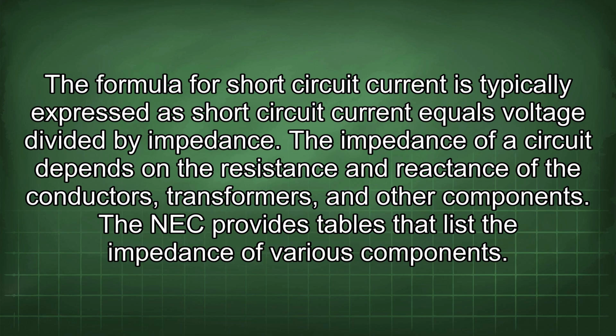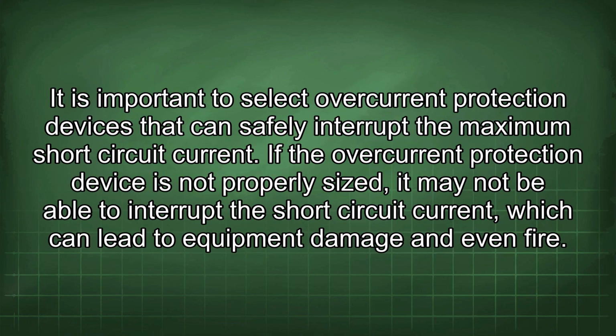The formula for short circuit current is typically expressed as short circuit current equals voltage divided by impedance. The impedance of a circuit depends on the resistance and reactance of the conductors, transformers, and other components. The NEC provides tables that list the impedance of various components. It is important to select overcurrent protection devices that can safely interrupt the maximum short circuit current. If the overcurrent protection device is not properly sized, it may not be able to interrupt the short circuit current, which can lead to equipment damage and even fire.